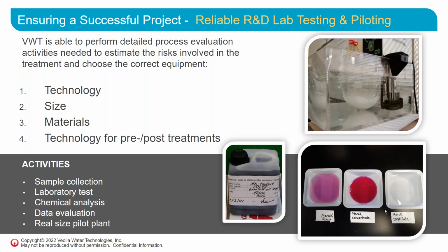But if we get to the point that it's a more practical project, we have a lab that we can send a few gallons of sample to and run a true distillation test. We do full analysis of the influent, the concentrate, and the distillate to show full and actual recovery rates of that waste stream. So it's a great pilot to be able to do to assure you. But again, we can typically give you a good rule of thumb from your process that you're dealing with.